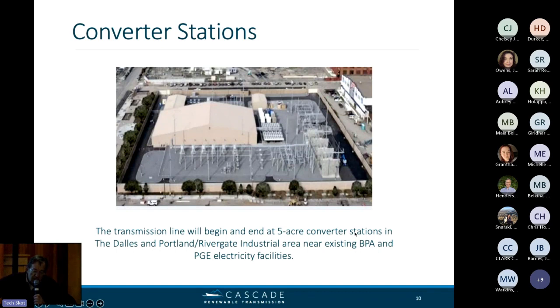The small building in the upper left-hand corner has the control system to handle the conversion process, plus part of the valve cooling system, also visible on the right-hand side of the building. The AC system is pretty small - there are 3 transformers, and it's compact on 5 acres. That's the extent of what a converter station looks like. Its noise profile is pretty friendly, all things considered, for this kind of equipment. There'll be 2 of those, one at each end.